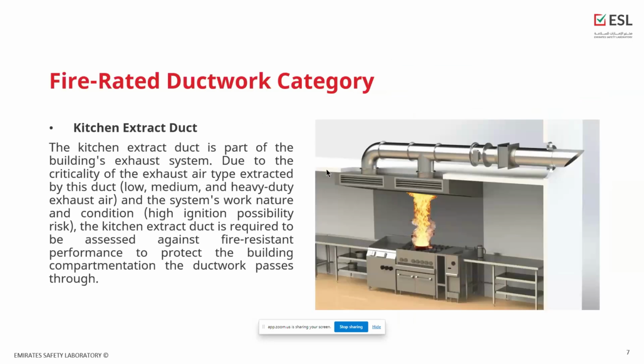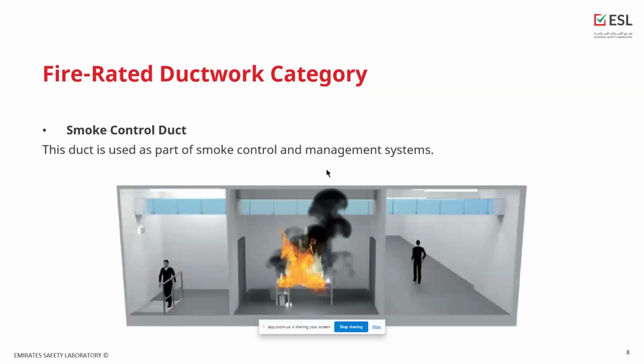And we also have kitchen extract. This kind of duct is crucial and needs attention, because firstly, of the nature of the work of the duct itself, it is working under difficult conditions in a very hot area, and at the same time the duct itself is containing combustible material. That's why in a lot of building codes and regulations we can see clear instructions and also limitations for this kind of duct. And we also have the smoke control duct, which serves the smoke control and management system during the fire.